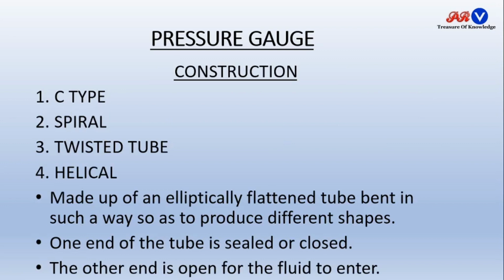Construction. So this pressure gauge can be constructed by using C-type Bourdon tube, spiral type Bourdon tube, twisted tube and helical tube, made up of an elliptically flattened tube bent in such a way so as to produce different shapes. Our elliptical tube is flattened, and it is bent so that we have C-type shape, spiral type shape, twisted tube shape and helical shape. One end of the tube is sealed or closed. One end of the tube is always sealed, while the other end is open for the fluid to enter, through which we can enter the fluid for pressure measurement.